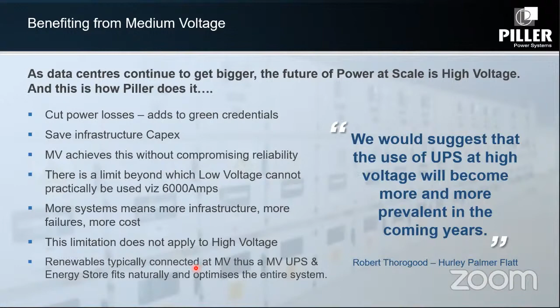So this is just a summary from a US client that was readily available. This is talking about a 10 MVA distribution. The voltage is 480 volts. It would change, but the overall effect would be the same. If you change to India, 415 volts. The comparison is 13.2 kV versus 480 for India. It could be 11 kV and 415. If you have a standard LV UPS, you have a step down. You step down the voltage to 415 for the UPS. Depending on the distance, you have a lot of cables, and you have losses on the cable.